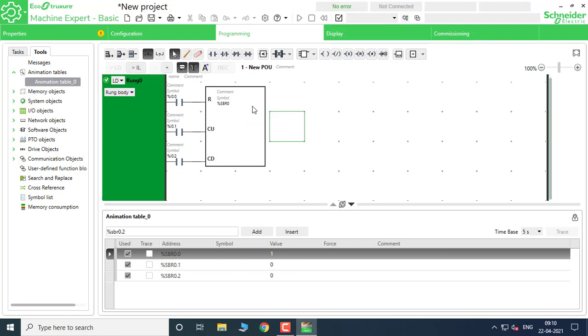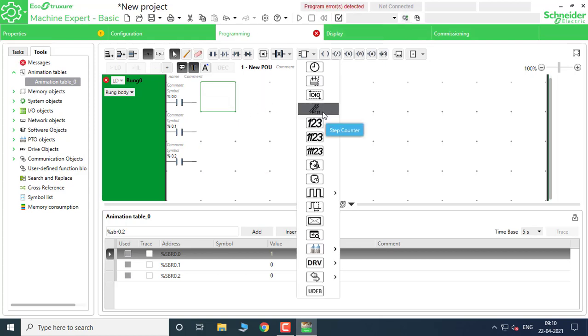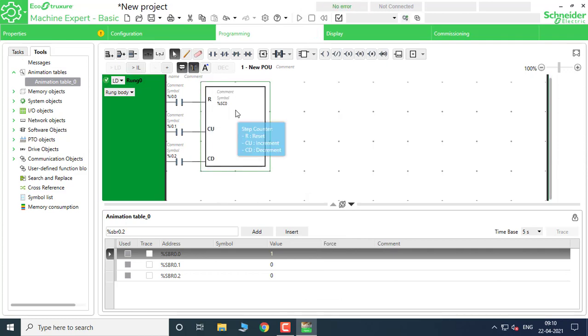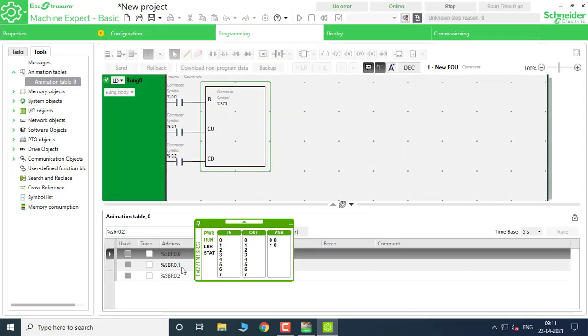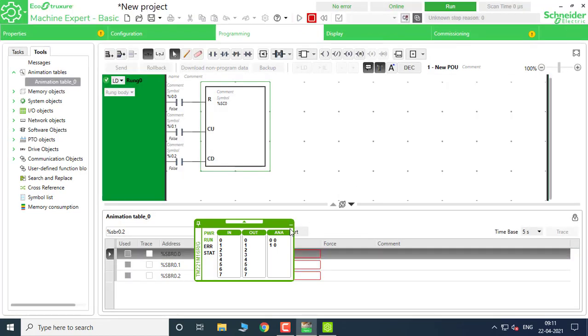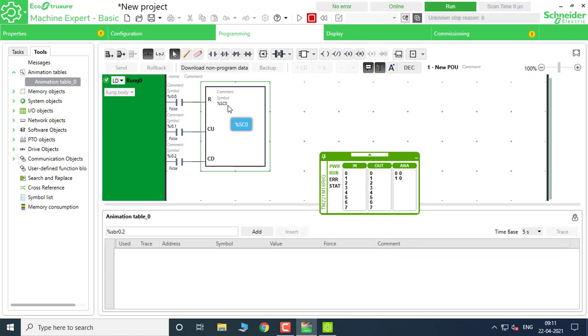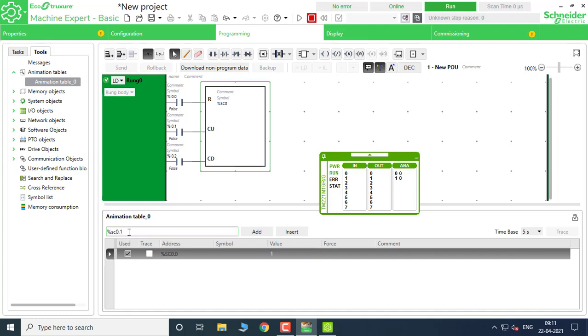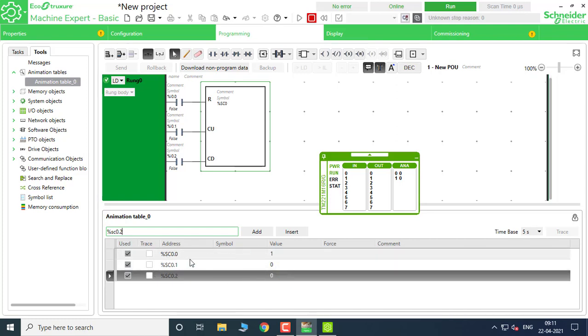The next function block is the Step Counter. I am placing the Step Counter here and launching the simulator. I don't need %SBR0.0 and SBR0.1 anymore and I am deleting those. I have to use %SC0.0, which is the address for the Step Counter. SC0.0 is the first address, SC0.1 is the second one, and SC0.2 is the third one. By default it contains SC0.0 — the first memory bit — with value 1.